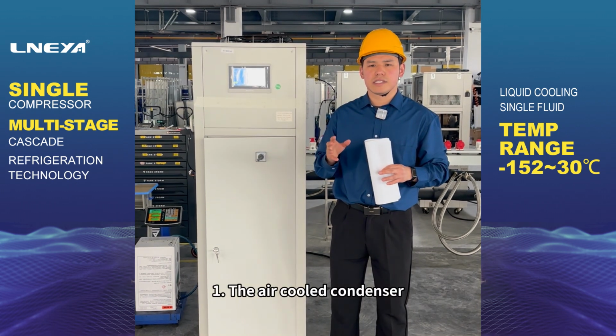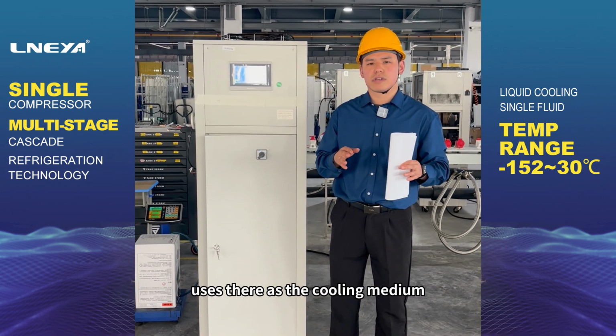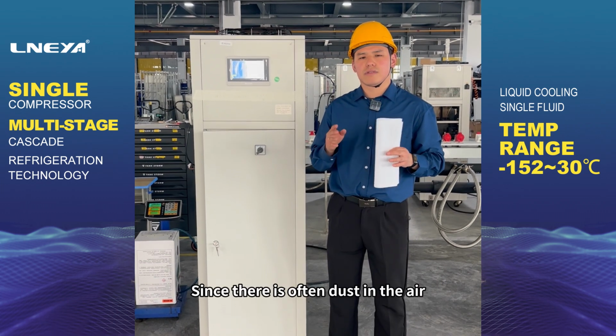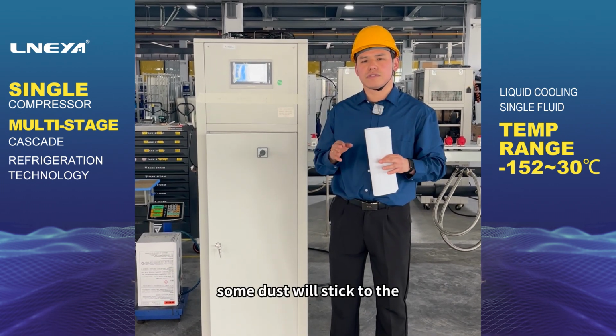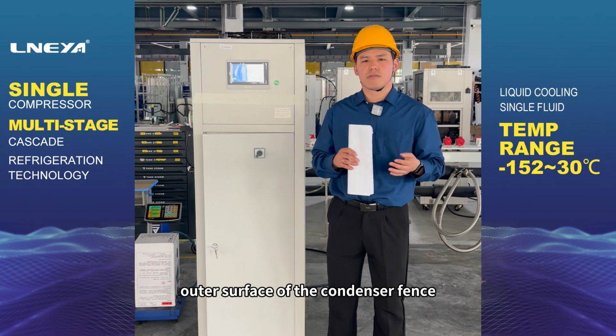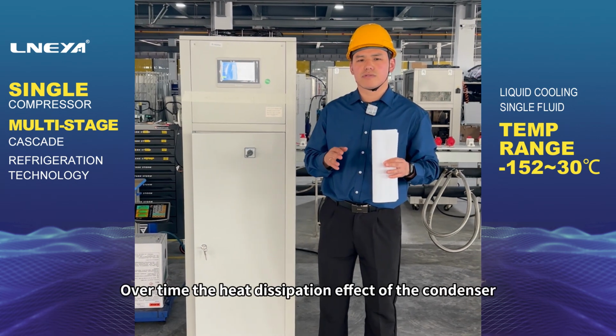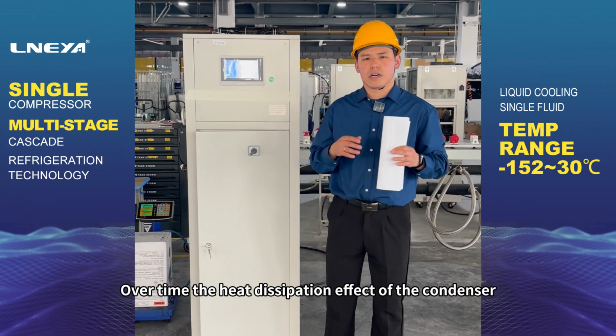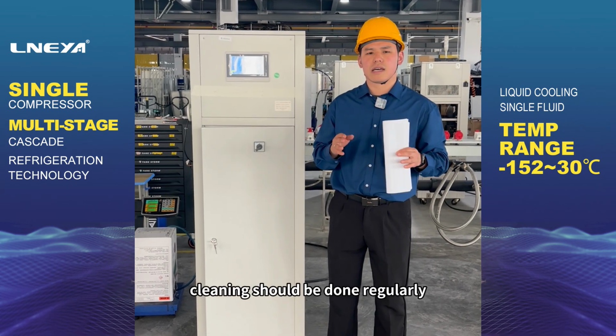The air-cooled condenser uses air as the cooling medium. Since there is often dust in the air, some dust will stick to the outer surface of the condenser fins. Over time, the heat dissipation effect of the condenser will become worse. Cleaning should be done regularly.